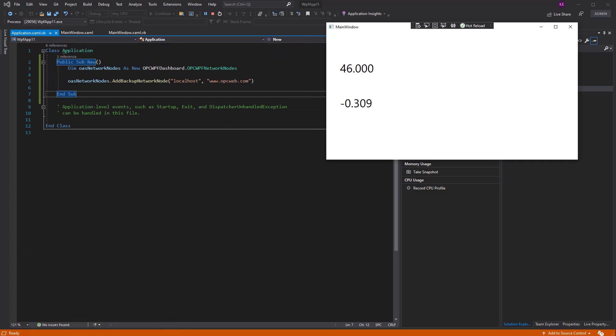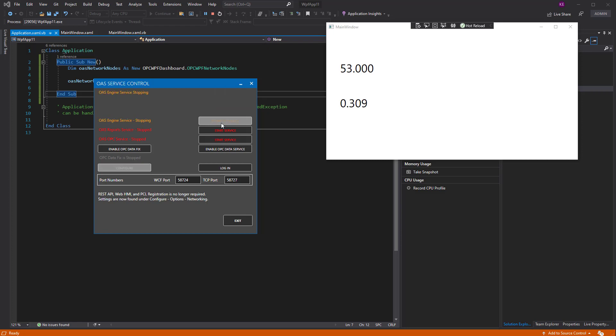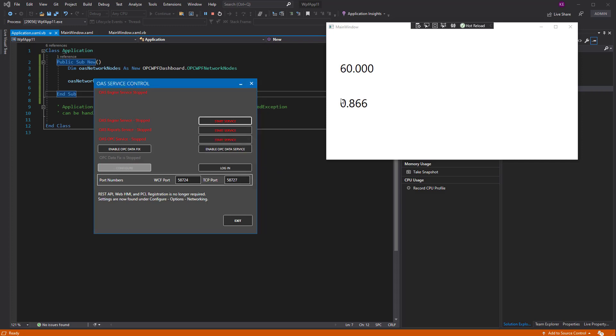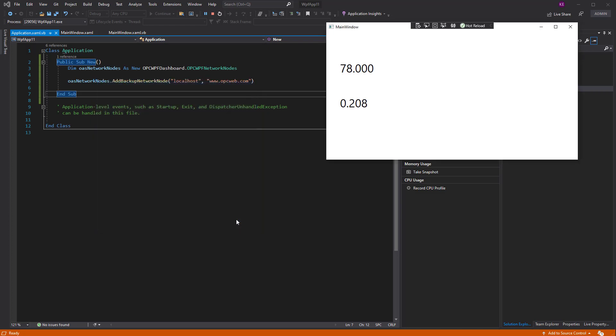This will also account for when the entire engine is not available. So let's do this. Let's actually stop the OAS engine locally. And there we see that the engine is indeed stopped. And we are still updating values from opcweb.com. And if we start the engine back up online, it will switch back to the local node as well. Of course, our simulation tag is back to a simulation of RAMP itself. So that transition, we really didn't see that.